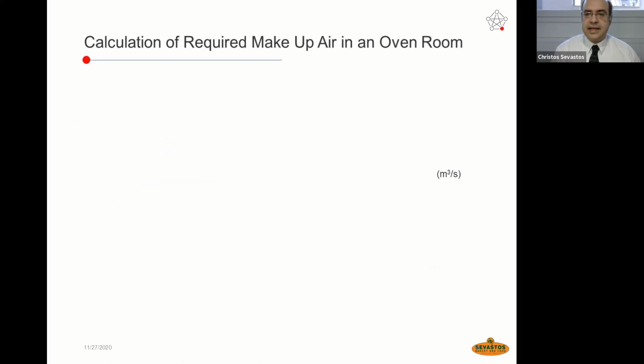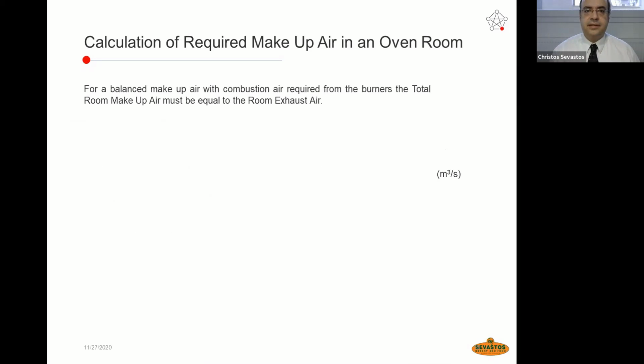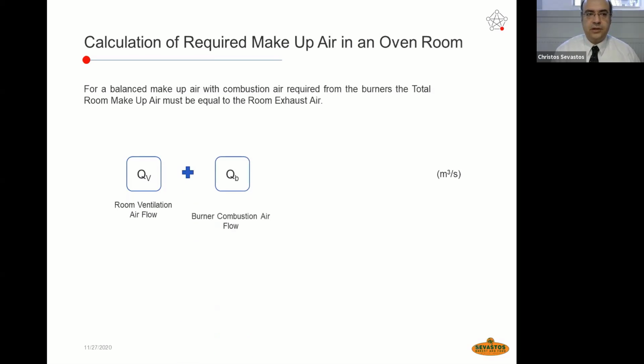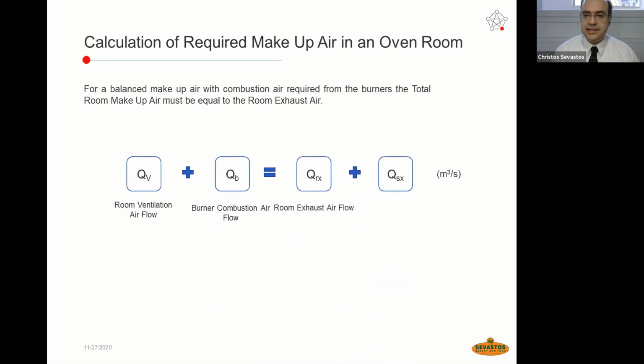Now, in the next slides, we may proceed with the calculation of the required makeup air in an oven room. For a balanced makeup air with combustion air required for the burners, the total room makeup air must be equal to the room exhaust air. So this is the mass balance equation, which is going to be implemented in order for us to define the QV, the room ventilation airflow.